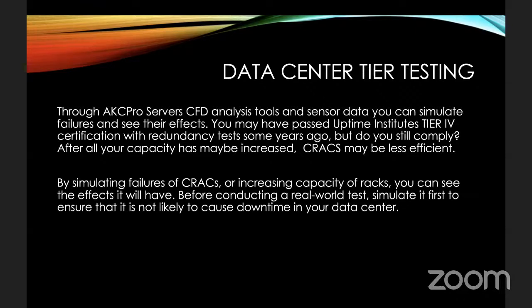Using our system, you will be able to simulate these failures. You can simulate what will happen if I turn off this crack. So in our software, you will be able to turn off a crack, and we will ignore the values from that sensor. And we'll be able to then simulate what would happen to your other crack units, whether they will pick up the load, or whether your servers are going to overheat, whether your delta T's are going to remain the same. This is based on the CFD model. So before you do any addition of capacity, you could run the simulated test and be able to see the results before you actually do it.